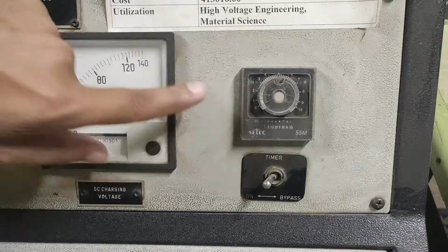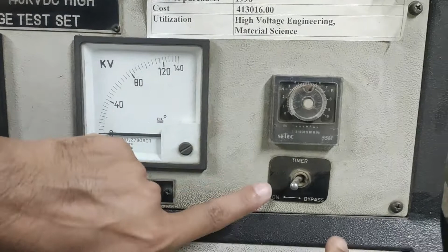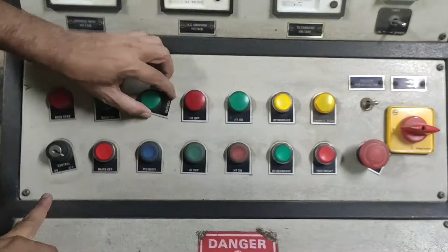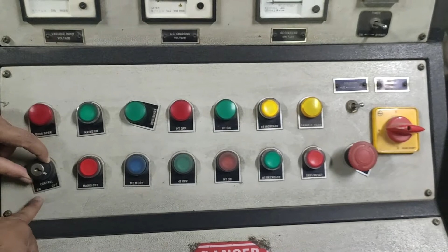Here again you can observe the timer switch, which is used to carry out the breakdown test as well as the withstand test. So we are going to perform a breakdown test, so we are bypassing this switch. And now some switching arrangement. The same switching arrangement is present. So for protection purpose we have one key switch in which we need to place one physical key so that we can turn on this test setup, because it is a 100 kV test setup, so we should be more precise.